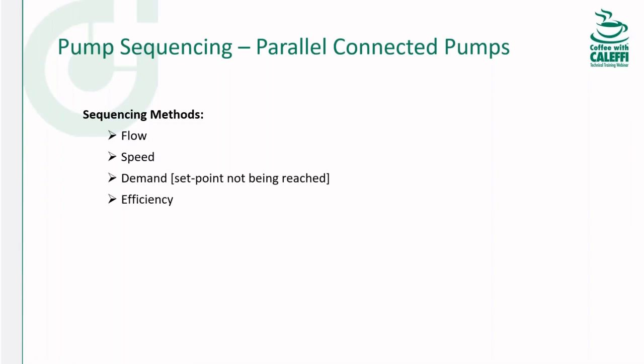And finally, we have efficiency-based sequencing. This takes into account efficiency, obviously, to determine optimal staging of the multiple pumps. In this scenario, the controller is continuously monitoring the applicable data points to calculate pump efficiency at the current operating point. This can be done by measuring suction and discharge pressures and back calculating flow, or, like Grundfos says, preloaded pump curves in the controller. Or if you have a flow meter, that'll even further increase the accuracy.